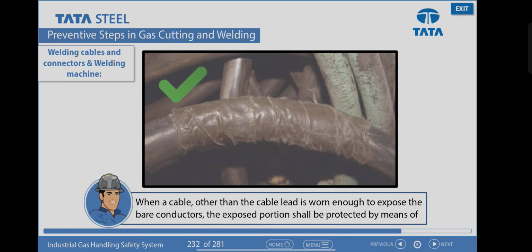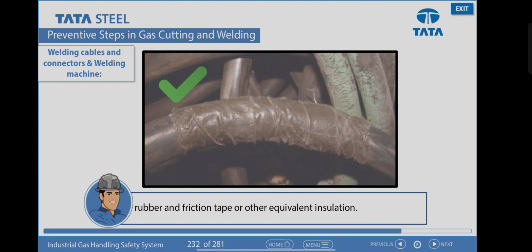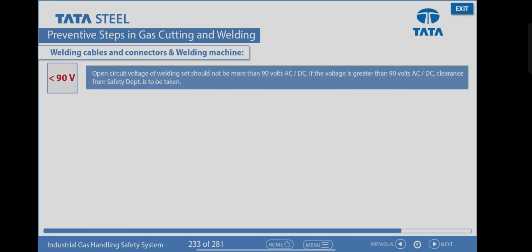When a cable other than the cable lead is worn enough to expose the bare conductors, the exposed portion shall be protected by means of rubber and friction tape or other equivalent insulation. All cable terminations should be properly made and shrouded. Open circuit voltage of welding set should not be more than 90 volts AC or DC. If the voltage is greater than 90 volts AC or DC, clearance from the safety department is to be taken.